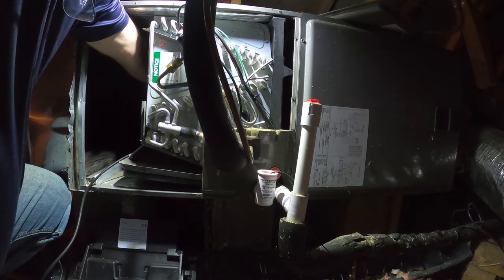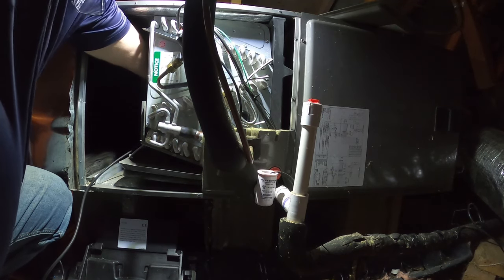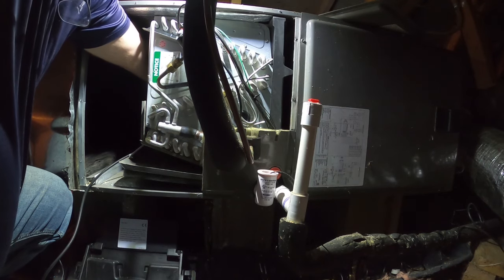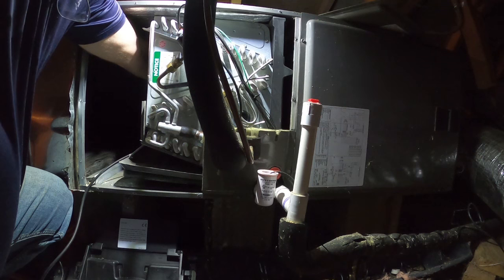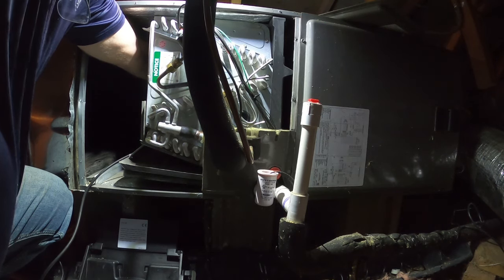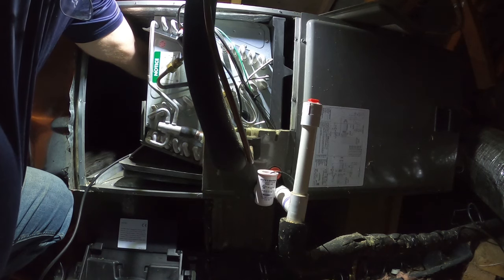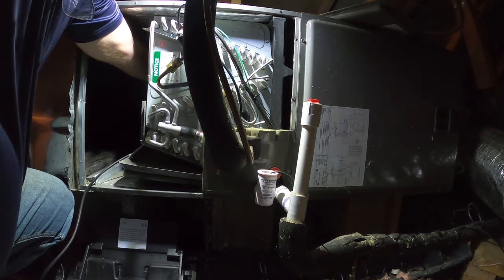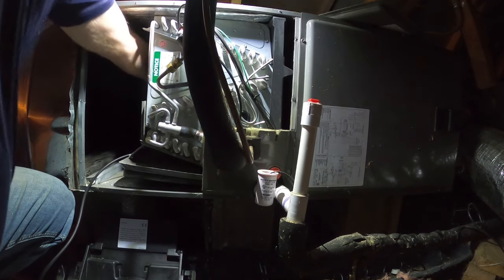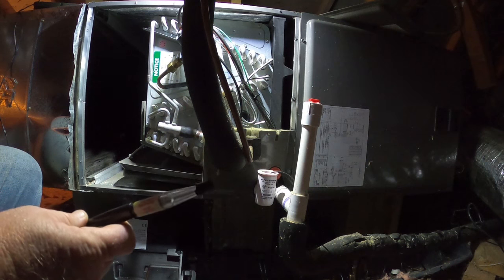And checking the back side of that coil down the edge. And this leak detector will start getting a little faster and a little faster. Right there. As I do manual calibration on mine, and you can set that sensitivity. There it is. Faster. It's a very small leak in that. And it'll slow down once it recalibrates to fresh air.